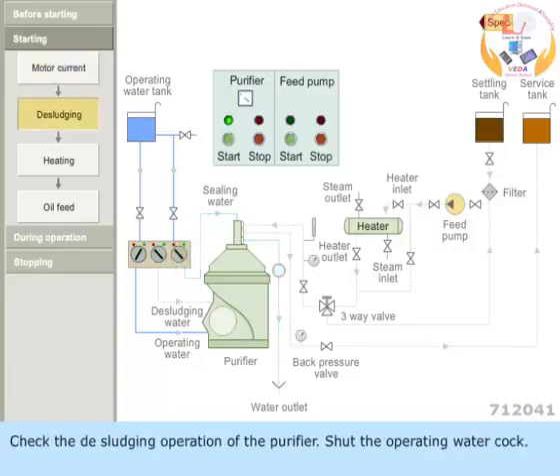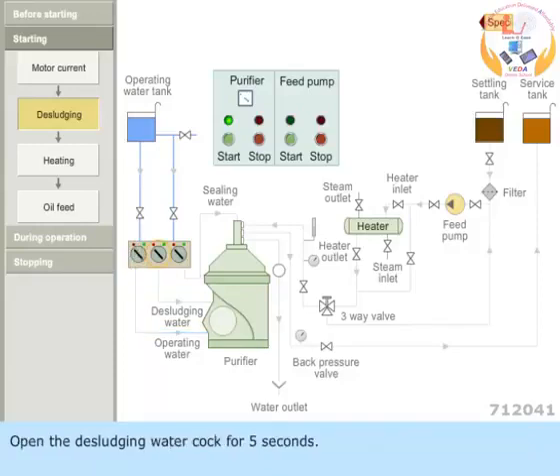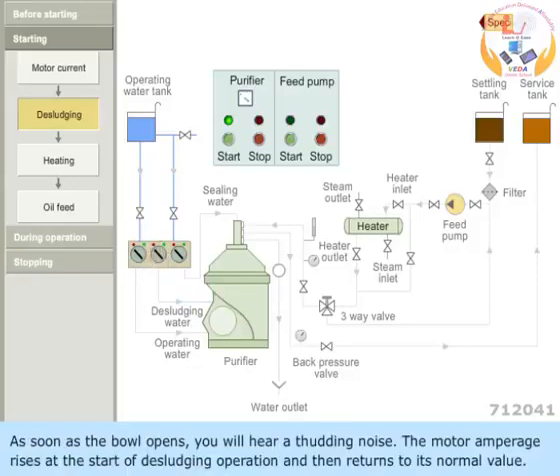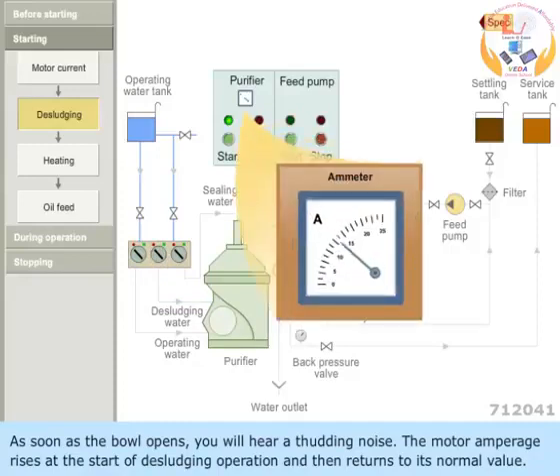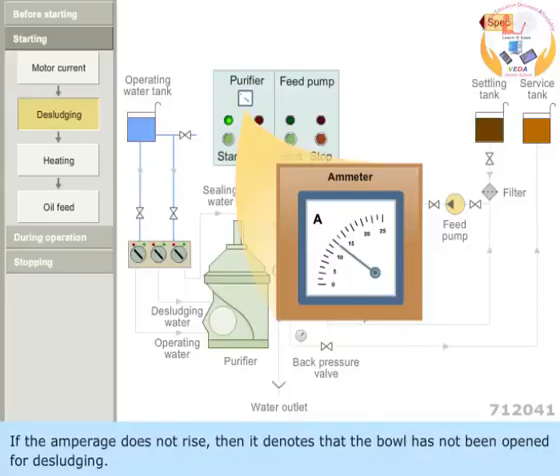Check the desludging operation of the purifier. Shut the operating water cock. Open the desludging water cock for 5 seconds and shut the cock. As soon as the bowl opens, you hear a thudding noise. The motor amperage rises at the start of desludging operation and then returns to its normal value. If the amperage does not rise, then it denotes that the bowl has not been opened for desludging.